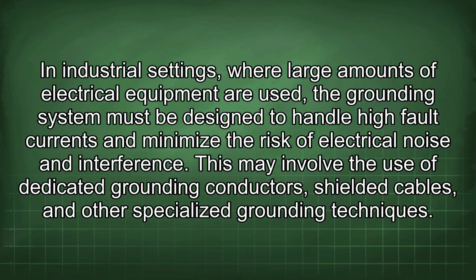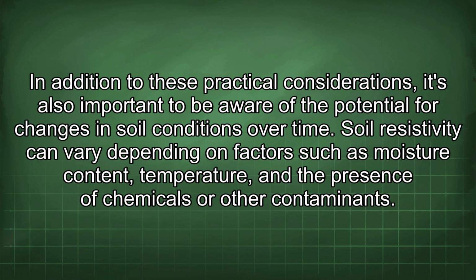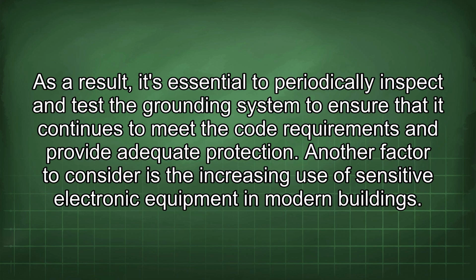In industrial settings where large amounts of electrical equipment are used, the grounding system must be designed to handle high fault currents and minimize the risk of electrical noise and interference. This may involve the use of dedicated grounding conductors, shielded cables, and other specialized grounding techniques. In addition to these practical considerations, it's also important to be aware of the potential for changes in soil conditions over time. Soil resistivity can vary depending on factors such as moisture content, temperature, and the presence of chemicals or other contaminants. As a result, it's essential to periodically inspect and test the grounding system to ensure that it continues to meet the code requirements and provide adequate protection.